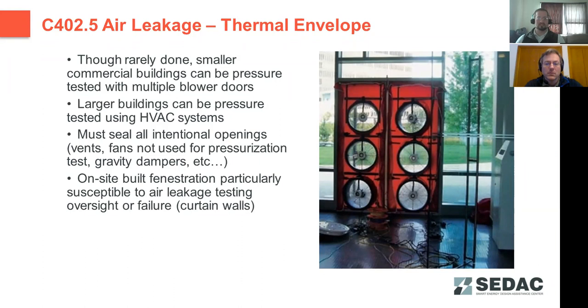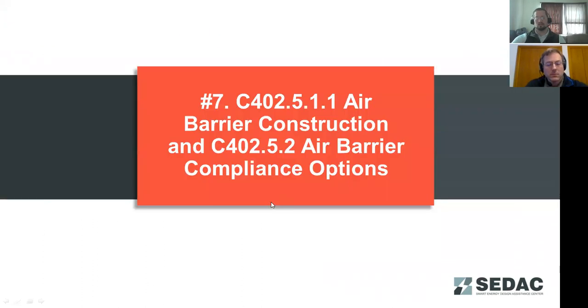To do that pressure testing, you have to seal all intentional openings in the building, so doors and windows have to be closed. For commercial buildings, it requires sealing off exhaust vents and things like that that would normally allow some leakage into the building, so that you can test the tightness of the envelope and not necessarily the tightness of your ventilation openings. One particular thing that we've noted in the past is that on-site built fenestration can be particularly susceptible to leakage failures. A lot of times this results in, down the road, you'll see sealant fall out of place on those windows and things like that. So this is a really good way to catch those hidden issues, such as site-built windows or areas of the building that might have tight corners and things that are hard to look at.